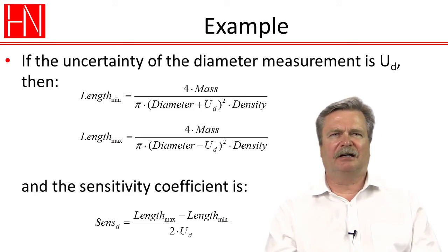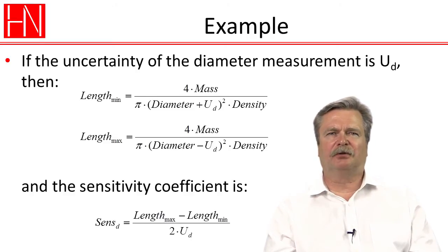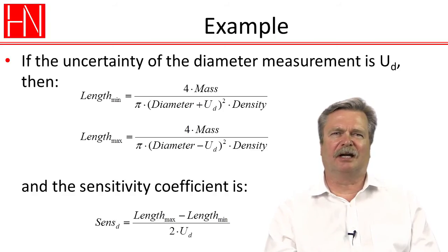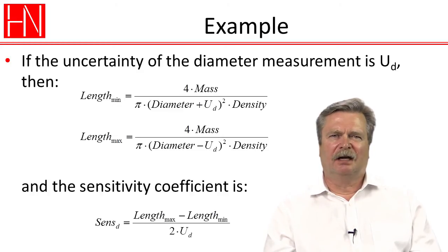And so here we have, for example, for the diameter measurement, we take the diameter and then we add the uncertainty of the diameter measurement to the measured value, and that gives us a minimum length. And then in the next equation, we subtract the uncertainty of the diameter from the value and calculate, and then we get a maximum length. And then from that, we can calculate a sensitivity coefficient, that is the difference in those two lengths divided by two times the uncertainty.